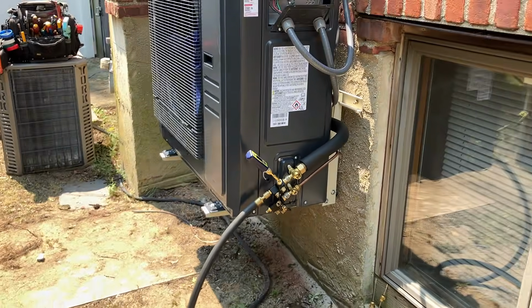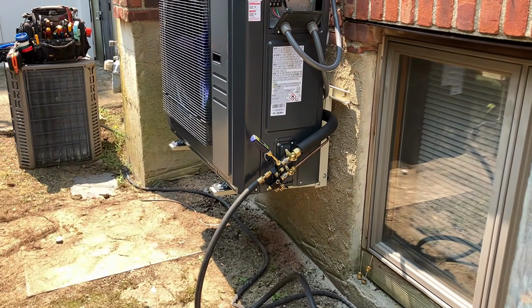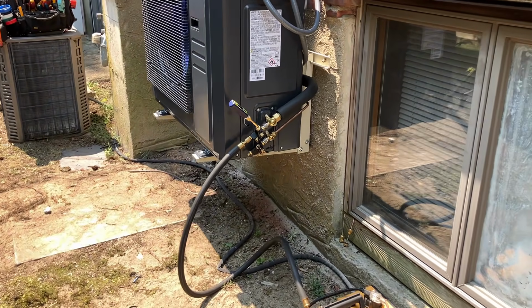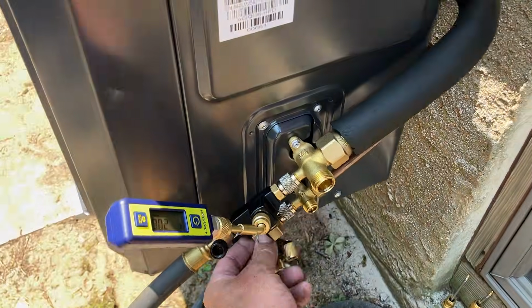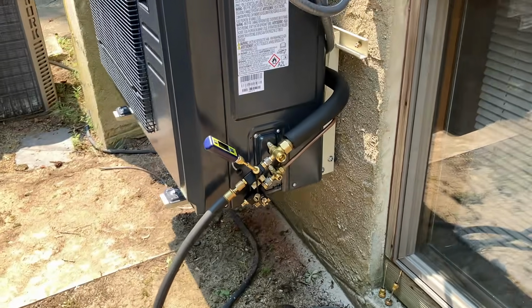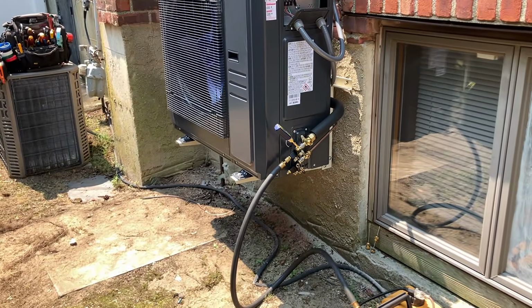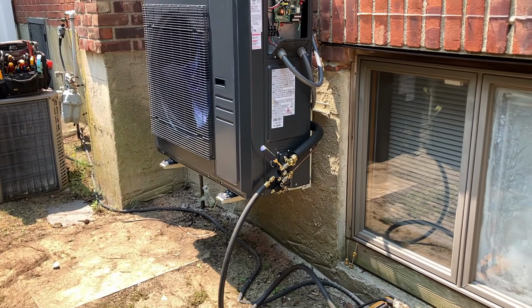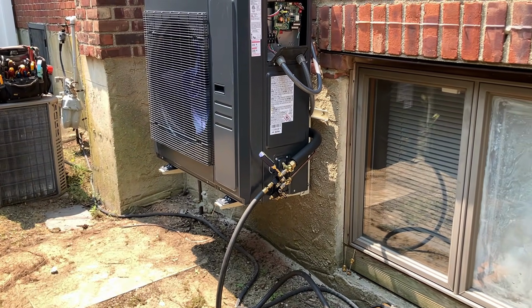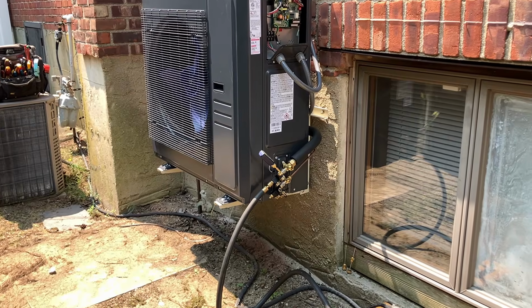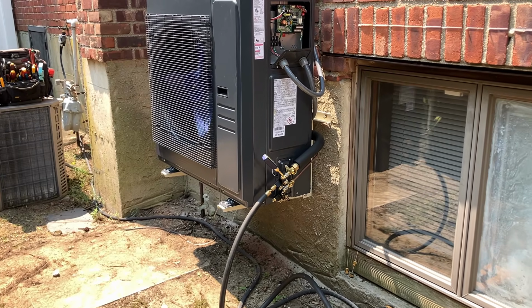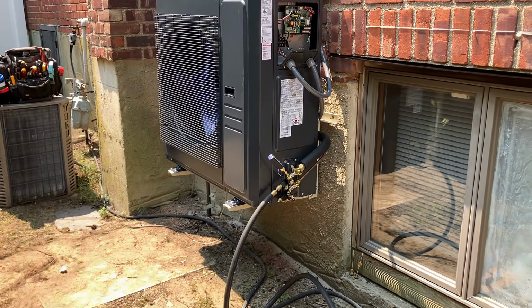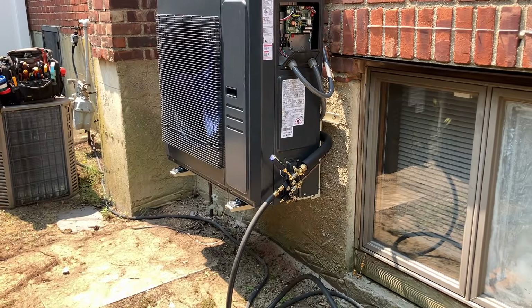But we're nice and tight and dry. This is a passing decay test. Let's shut down the vacuum pump. Actually, you know what? Let's give it some more time. I'm in no rush. Daniel is just about finishing up in the attic, wiring in the condensate switches on the primary and emergency drain lines. And there's no rush. What is this gonna take? Another 10 minutes? Whoopie-doo.